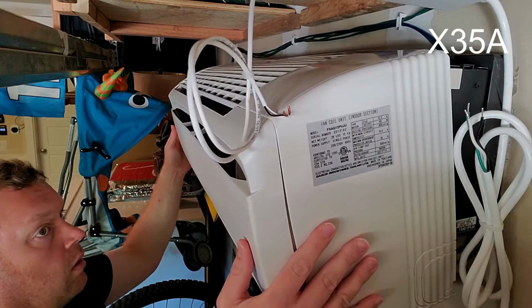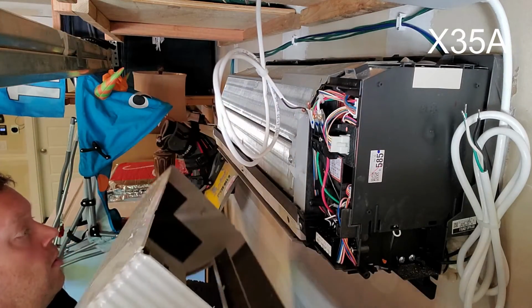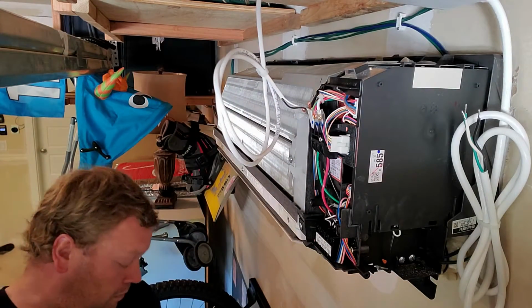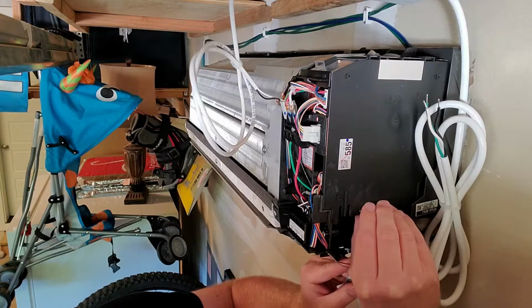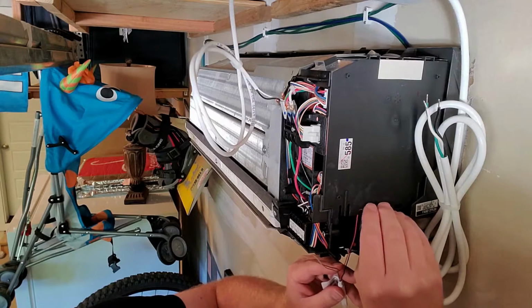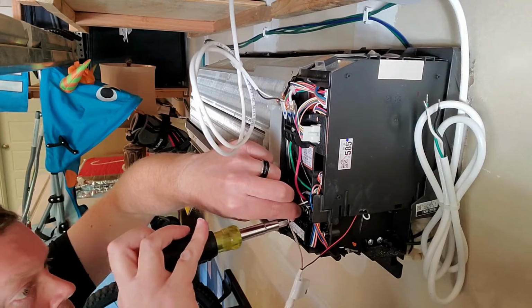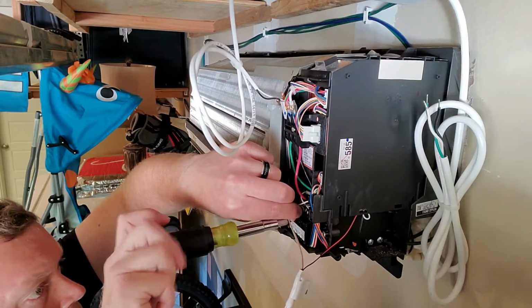The first thing that you're going to need to do is locate the X35A connector. Now, depending on what indoor unit you have for VRV products, it's going to potentially be in a different spot on the board. The nice thing about the wall mount is the connector is going to be right at the bottom, easy to access, right next to your condensate float switch. So go ahead and plug that 2-pin connector into the X35A connector, and then you're going to take the two loose wires and connect those to the P1, P2 terminal.